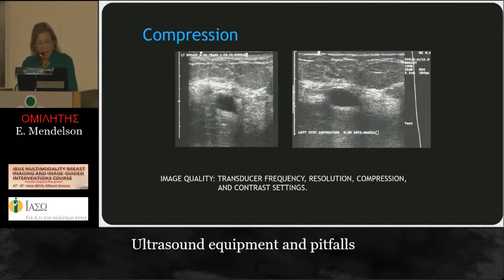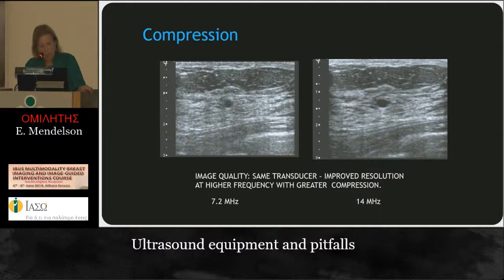And then if you go to another technique, with the same transducer and the same instrument being used here, with some compression, you are able to penetrate better through the tissue. You can see it a little bit better. It was a simple cyst, but here on the left, it's non-diagnostic. So watch the gain, the focal zone settings, and the resolution that you are achieving with your transducer.